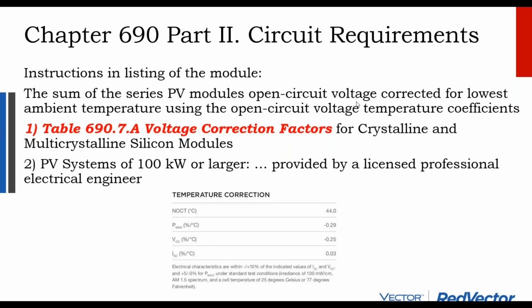And so we have a temperature correction chart that's built right into electric code that gives you an assumption factor that says we're going to assume the temperature correction factor is this. And so you look at the operating conditions of the array, and then you apply these temperature correction factors, and they have them for amperage, they have them for voltage. A volt times an amp is a watt. So there's also one for the combined two, the power.